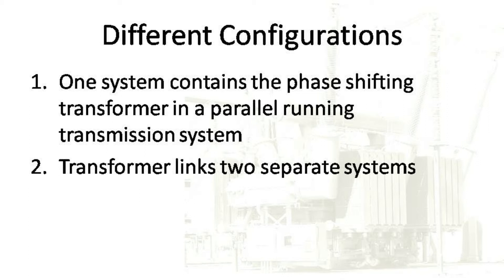The two active components may be placed in a single tank in lower power rating scenarios. Nevertheless, for bigger phase-shifting transformer applications, the two active components — the exciter and the booster transformer — will be installed in separate tanks but still connected together. The connection between these two components is conducted at maximum system voltage, and must usually be conducted inside oil-filled trunking in order to protect against the possibility of damaging internal short circuits.